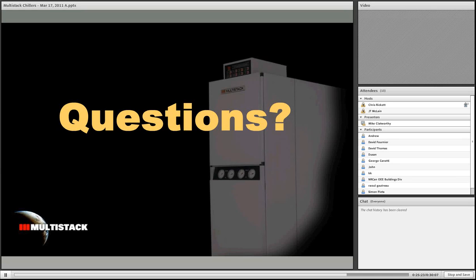So let's see, we've got another slide that has come up blank on us. All right, this was my VME2 simultaneous load performance summary, where I showed geothermal water temperature at varying temperatures and the associated efficiencies. Probably the most important takeaway that we can't see is that eliminating reversing valves and lifting the heat right out of the chilled water into the heating load improves my efficiency by up to 43%. It's substantially more efficient.